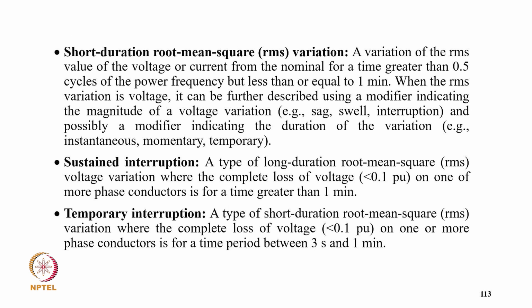Short duration RMS variation: a variation in the RMS value of the voltage or current from nominal for a time duration from 0.5 cycles of the power frequency but less than 1 minute. When the RMS variation is voltage, it can be further described using a modifier indicating the magnitude of voltage variation, and possibly a modifier indicating the duration of the variation, like instantaneous, momentary, temporary. Sustained interruption: a type of long duration root mean square voltage variation where the complete loss of voltage, less than 0.1 per unit, on one or more phase conductors is for a time of more than 1 minute.